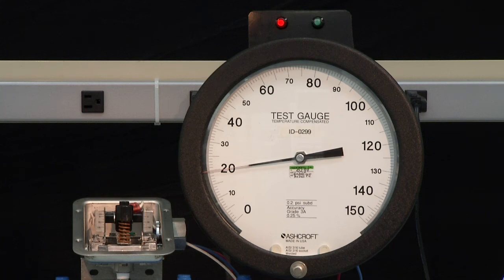And then we will raise it up to the point at which it turns on, which is just about 22. So it's approximately 2 psi dead band on this switch.